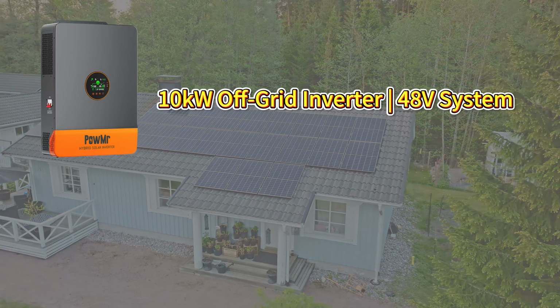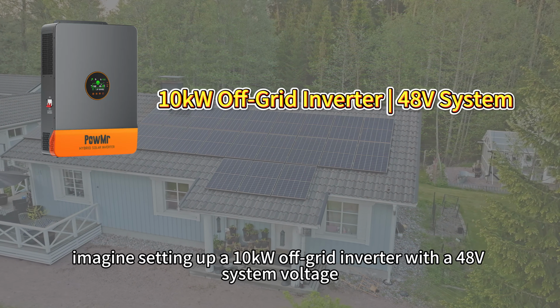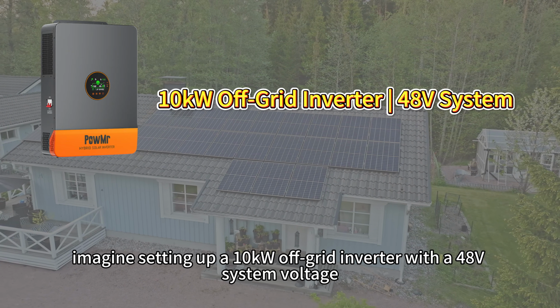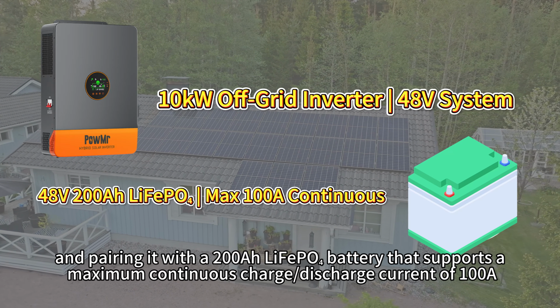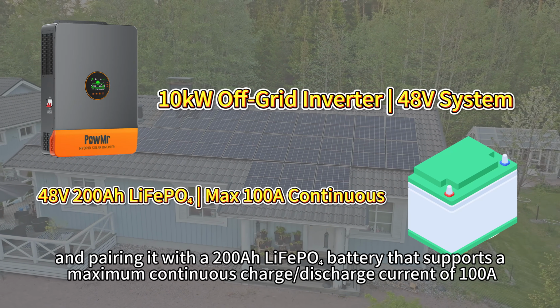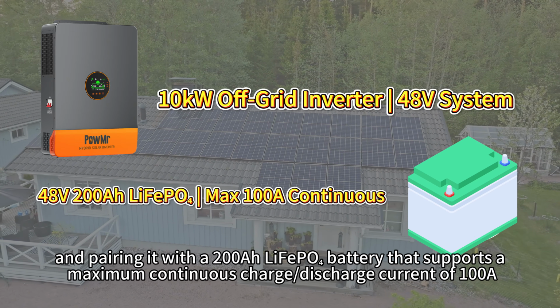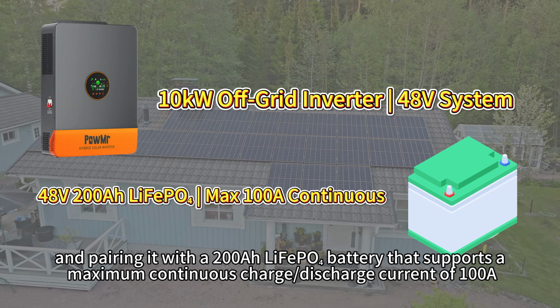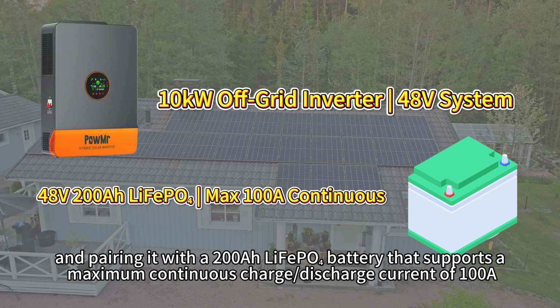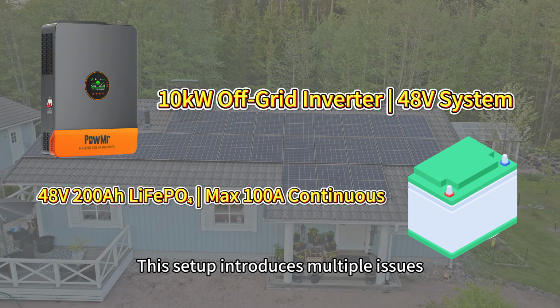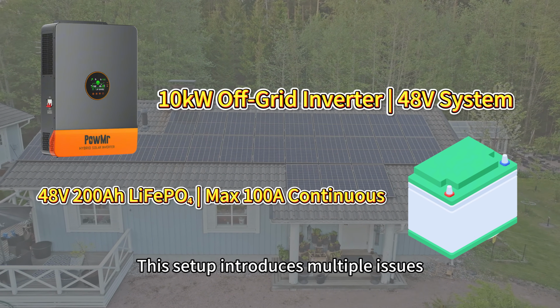For example, imagine setting up a 10 kW off-grid inverter with a 48-volt system voltage and pairing it with a 200 amp-hour lithium iron phosphate battery that supports a maximum continuous charge or discharge current of 100 amperes. This setup introduces multiple issues.